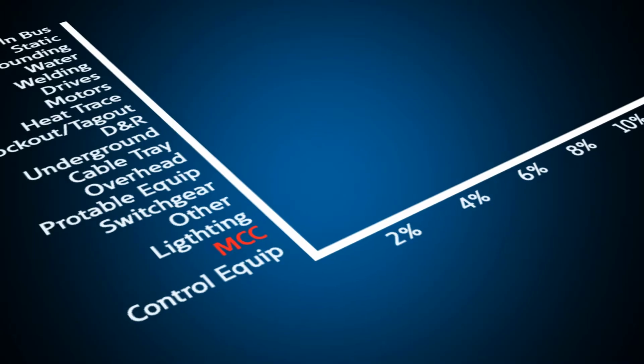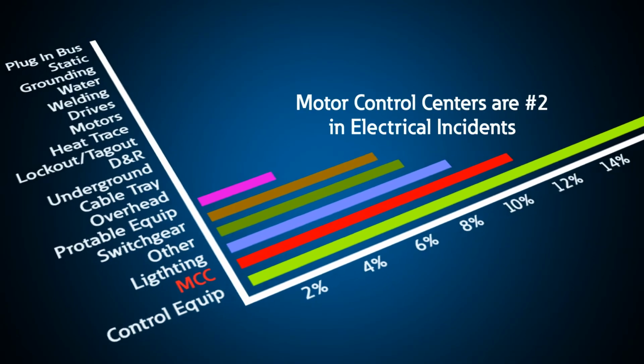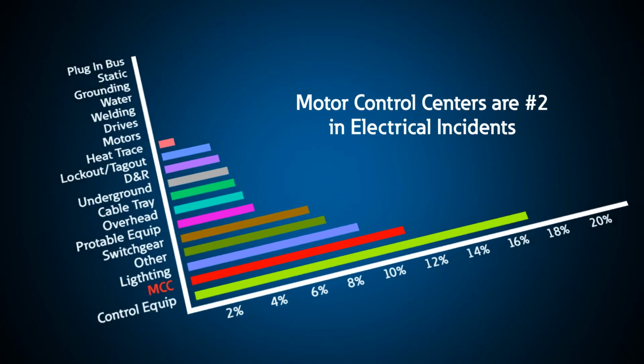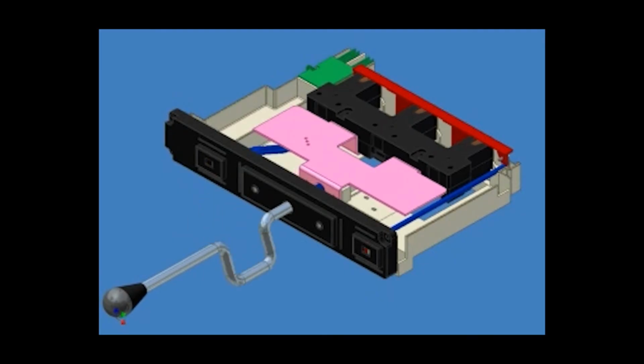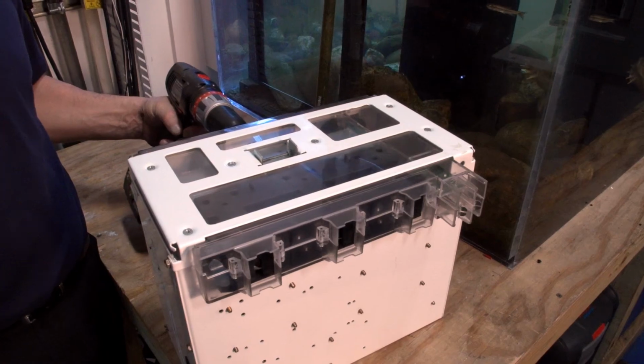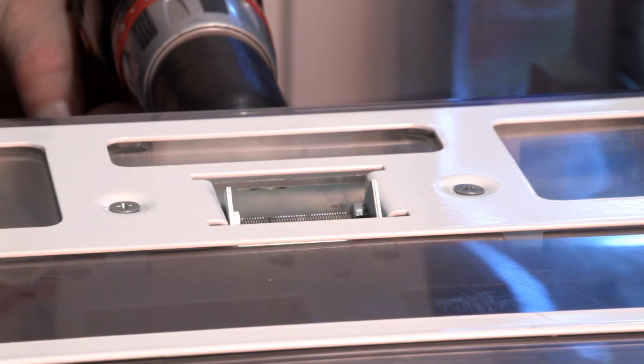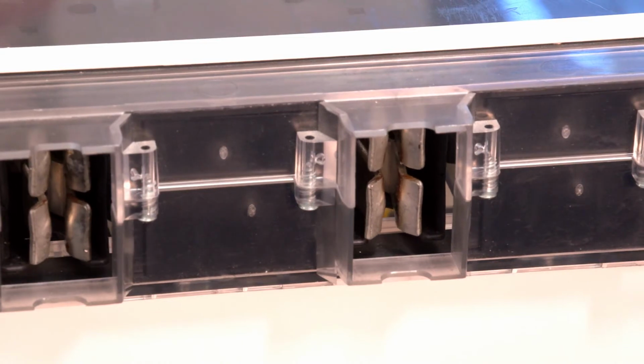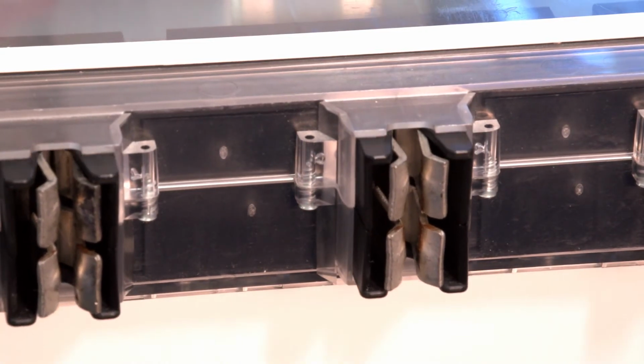One of the most common times for an arc flash event to occur is when adding or removing a bucket in a motor control center. This flash guard bucket can be added or removed with the door shut, with a local or remote operator protecting the worker until the bucket is safely removed from the energized bus. This flash guard MCC takes the procedures and guesswork out of your hands, only allowing the disconnect from live bus operation to be done exactly the same way each and every time.